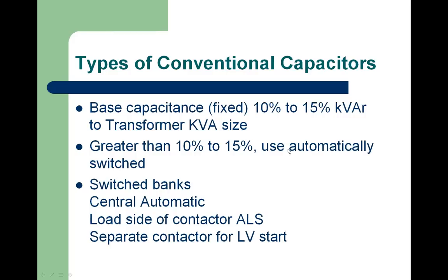So anything more than 10 to 15% of the kVA of the transformer, we would use an automatic switch bank that you saw earlier. There's some pictures of that.